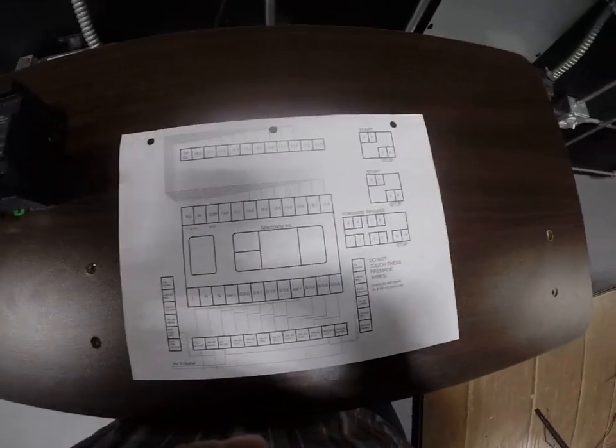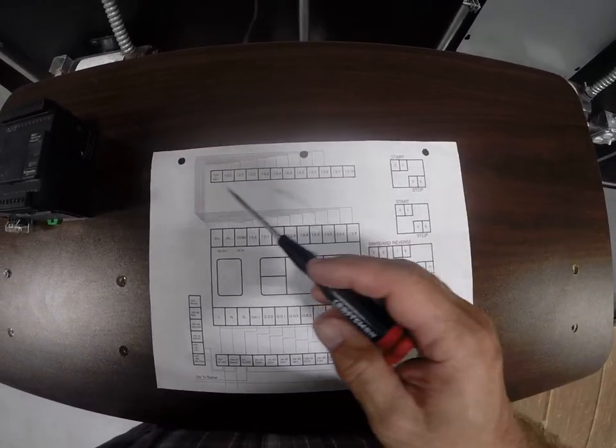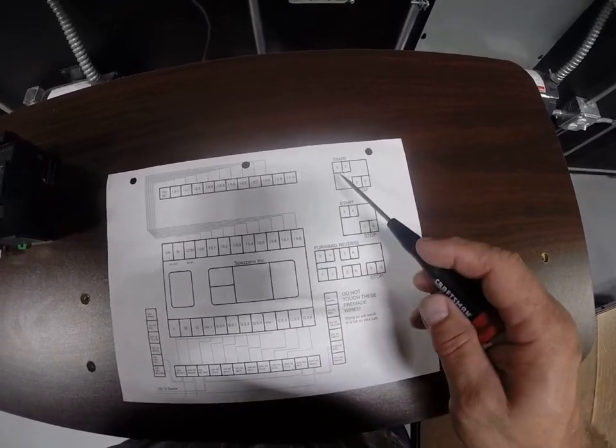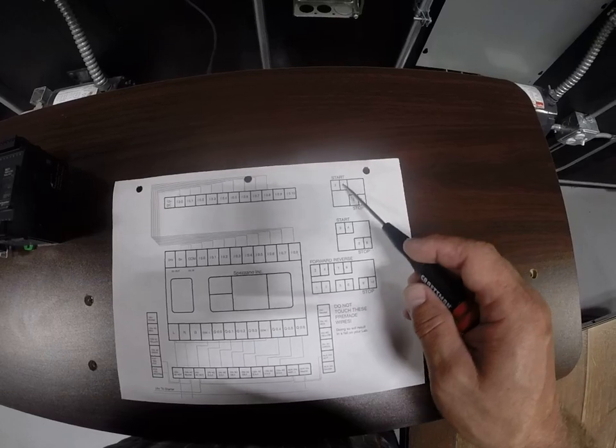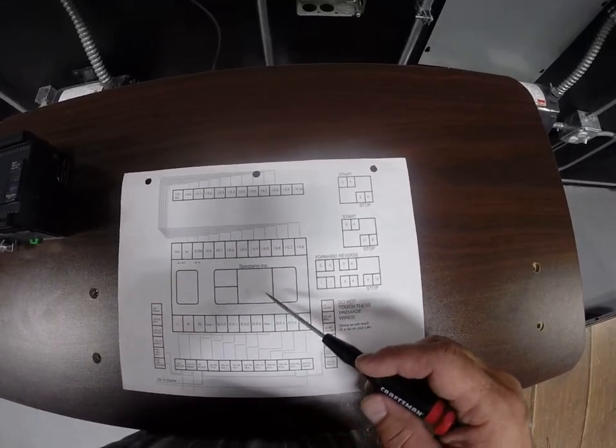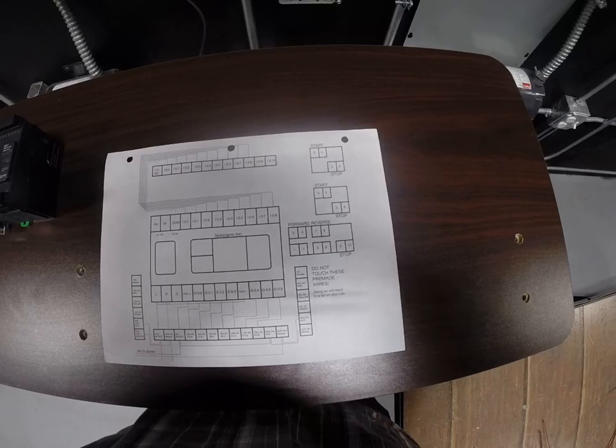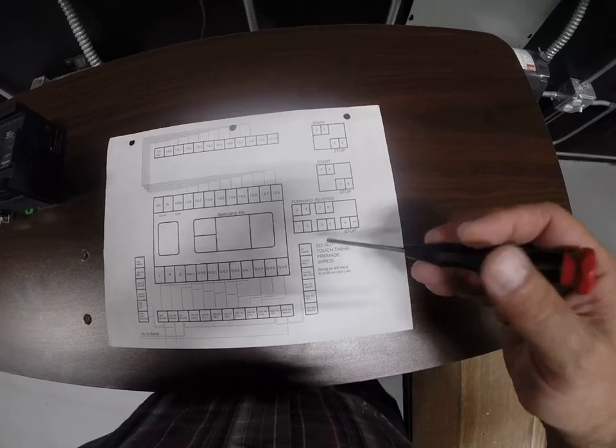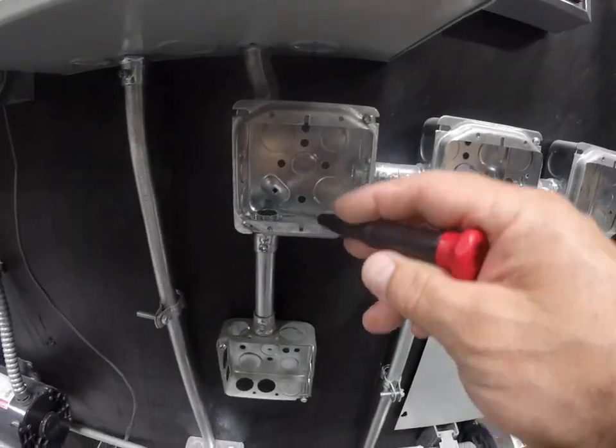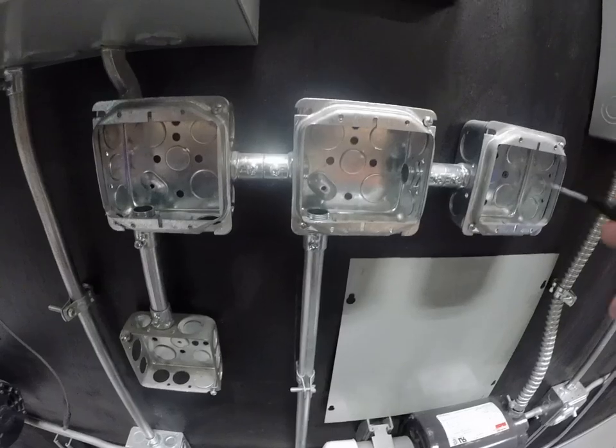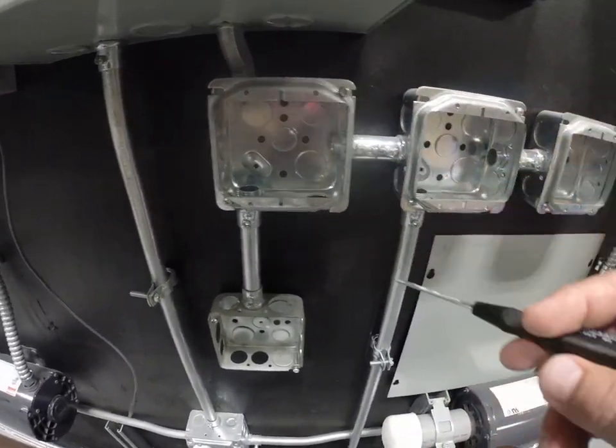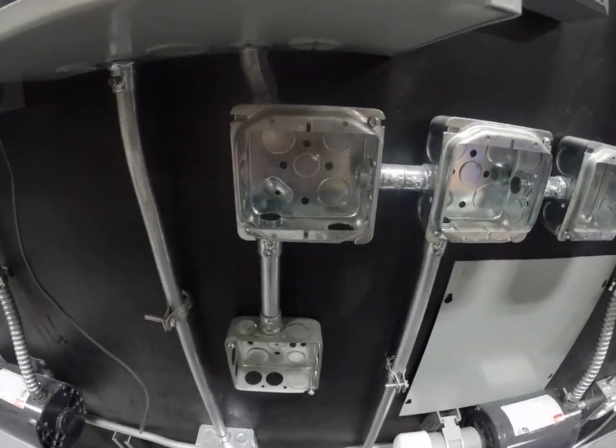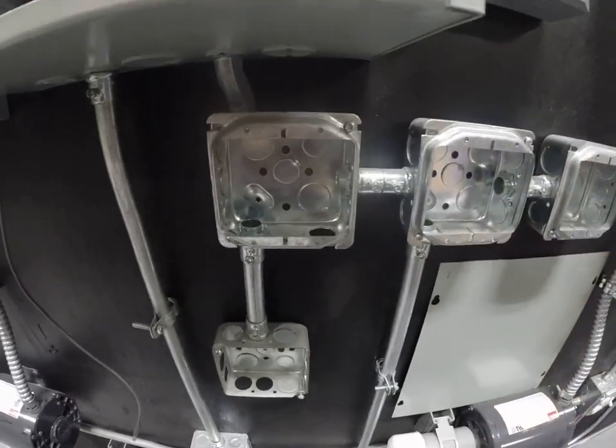Our mission, before we even attempt to wire anything on the PLC, is to understand how to take 12 volts into a switch by drawing a pencil line nicely neat, how to come off of your switch back to an input, and understand the sequence of operations. Because you're going to need to simulate this circuit by pressing buttons. They may not be just stop-start buttons, they may actually even be single-pole switches that we're going to put in here to represent pressure switches, float switches, solenoids, overload switches, temperature switches. There's a variety of different things we could simulate with single-pole switches.